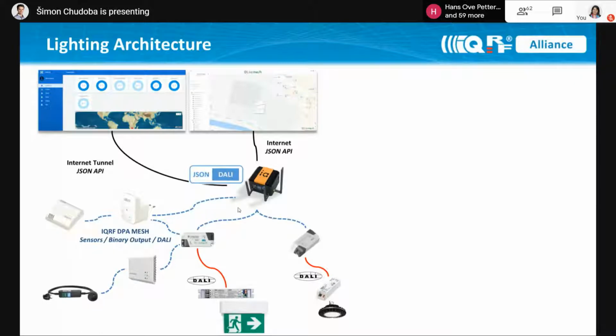Just to explain a little more: the DALI commands can go directly from the IoT platform down to the end node. You put the standard DALI command into the JSON protocol, send it to the gateway, and the gateway translates that, putting the same DALI command into the IQRF packet. The packet goes through the IQRF mesh network till it reaches the IQRF DALI bridge, and from there the DALI command goes onto the DALI bus, and with that you can, for example, switch on the light.